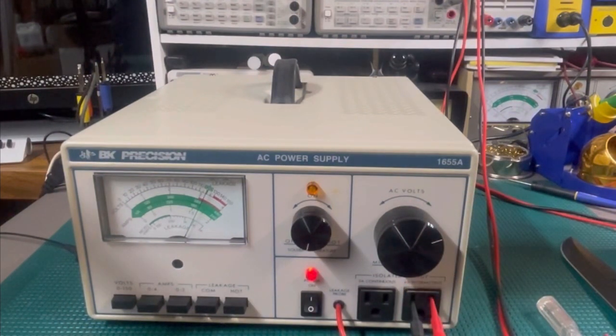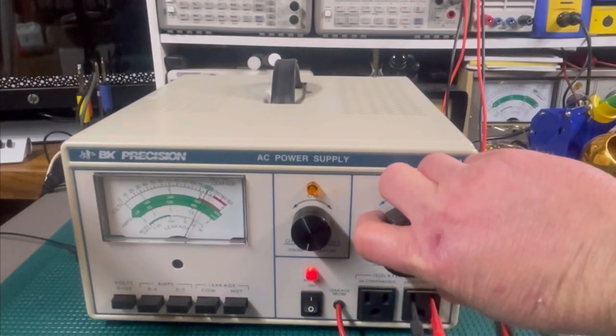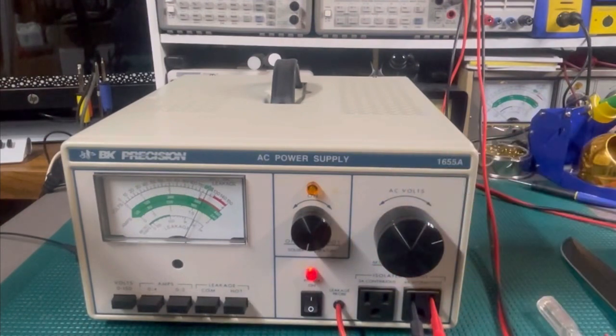120, we're only at 115. Or well, 114 technically. And oh well, there's a little bit of parallax. Let me adjust it up a bit. So that's bang on 120 on the gauge. Still 114.